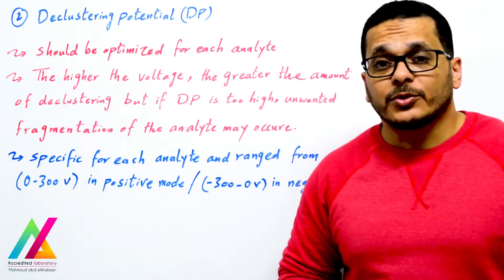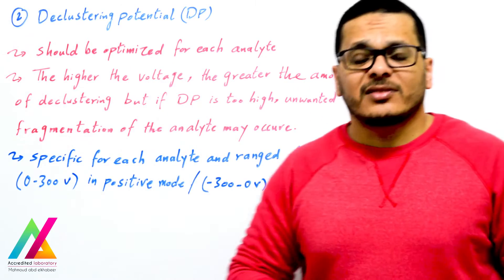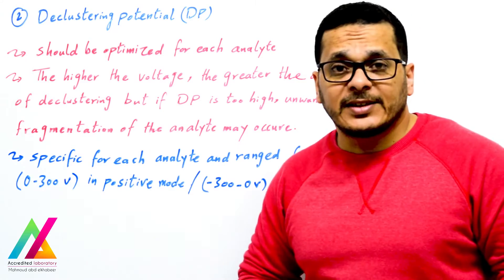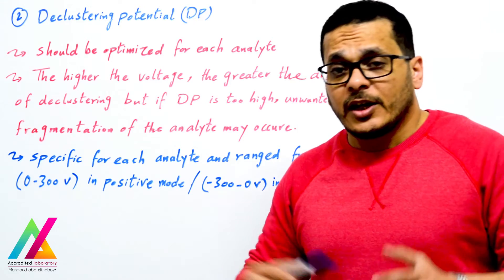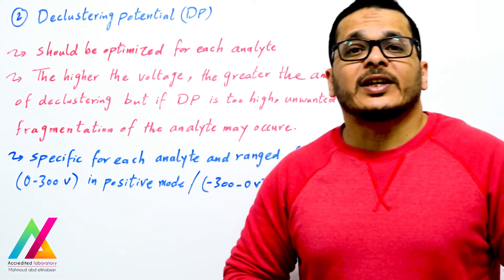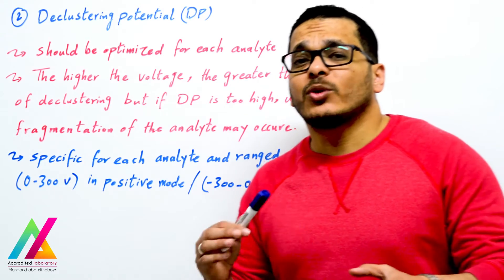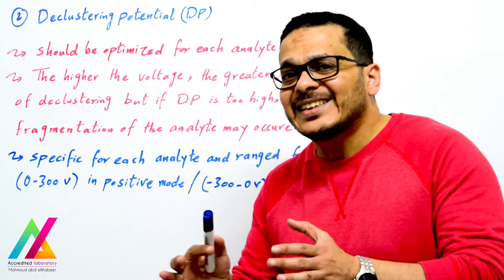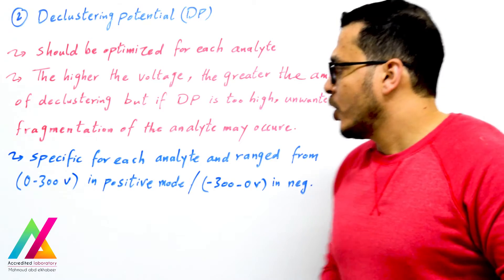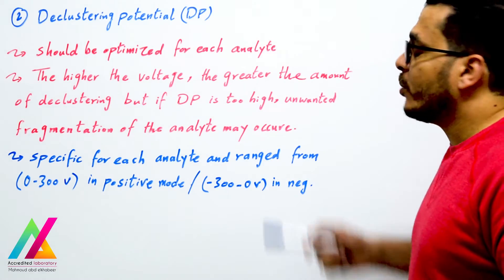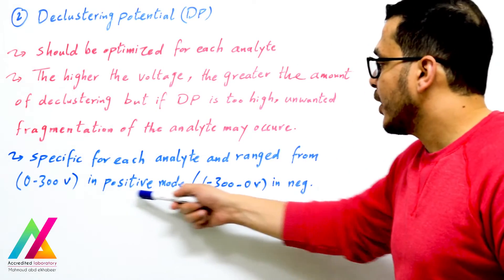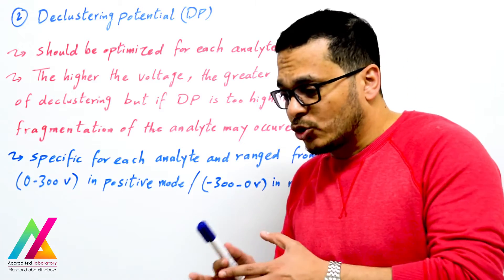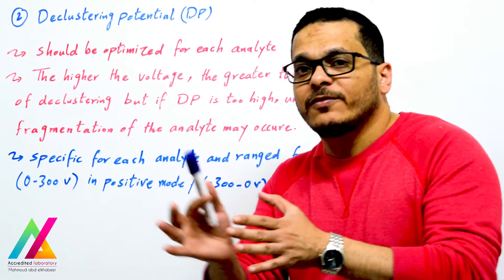The declustering potential (DP) is a very important parameter in your acquisition method. It should be optimized for each target analyte because there will be a specific DP for each analyte. The higher the voltage applied, the greater the declustering of solvent cluster ions. However, if you increase DP more than enough, your analyte ions may also be fragmented. So you must find the optimum DP for each target analyte, ranging from 0 to 300 volts in positive mode and from minus 300 to 0 volts in negative mode.